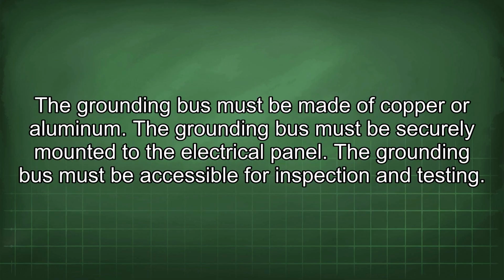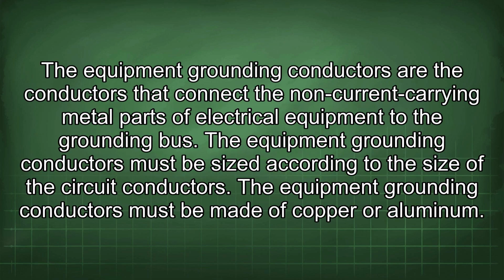The grounding bus must be made of copper or aluminum. The grounding bus must be securely mounted to the electrical panel. The grounding bus must be accessible for inspection and testing. The equipment grounding conductors are the conductors that connect the non-current carrying metal parts of electrical equipment to the grounding bus. The equipment grounding conductors must be sized according to the size of the circuit conductors.